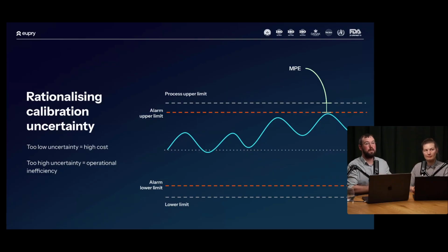Sometimes we see organizations choosing extremely low uncertainties, and that's going to have a very high cost. As an example, if you're storing something in controlled room temperature, which is a little bit different in the EU than the US, but in the EU at least it's 15 to 25 degrees, you have 10 degrees there, then 0.5 degrees is not going to matter that much.